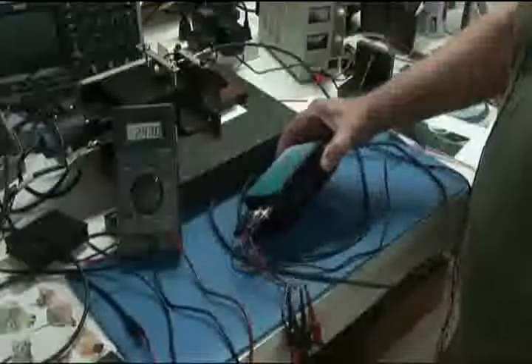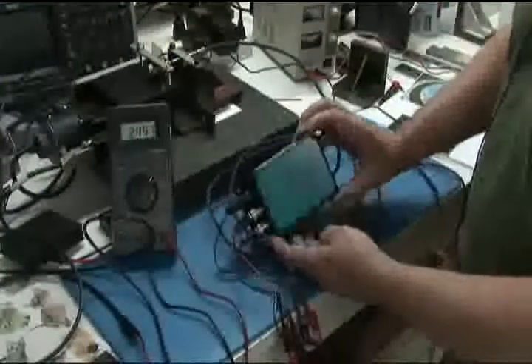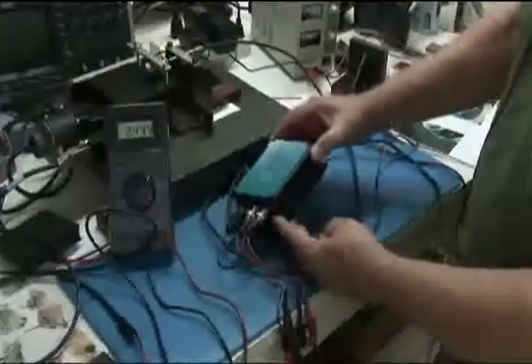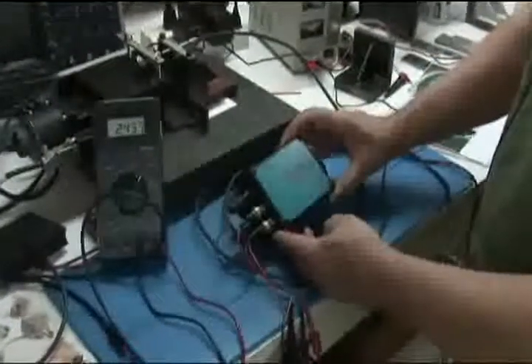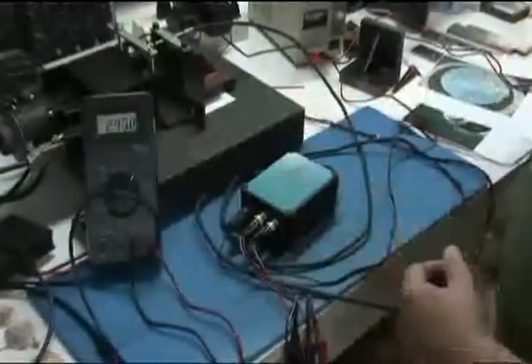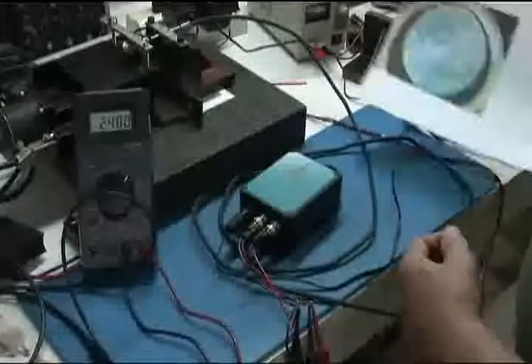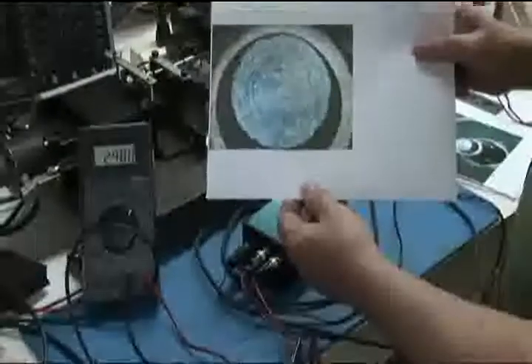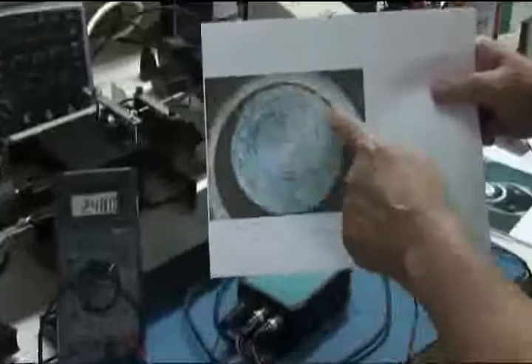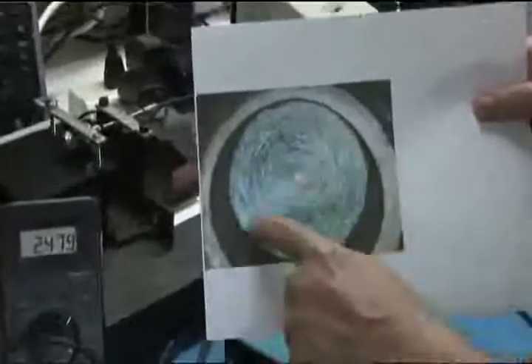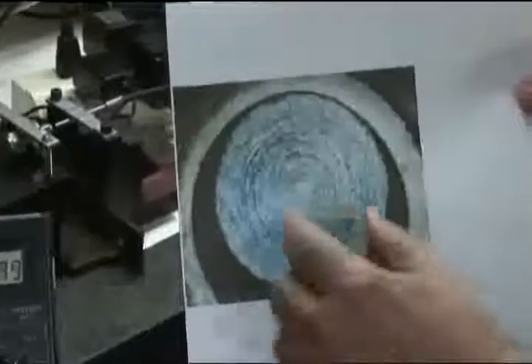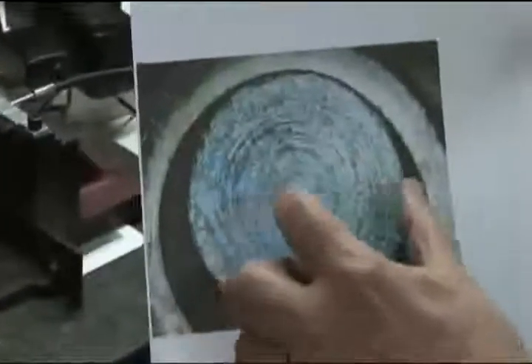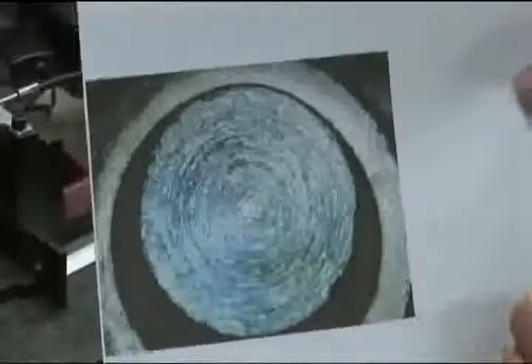I have one of your sensors here, and I want to describe to you how you need to set up and operate them, because the target plug that you've got is extremely rough. And here's a close-up picture of the pin. The end of the pin is just rough turned, and because it's so rough, little shifts of the sensor changing the position really make a large change in the sensor's output.